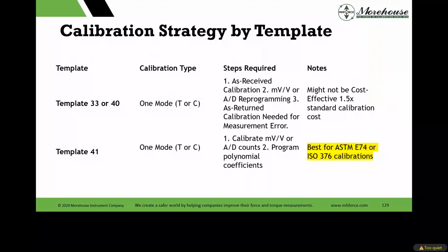So ideally, some of your problems with TEDS, which we started talking about bias and everything, is these templates, 33 or 40, the way TEDS is designed, is one mode. If I have a tension and compression load cell, unless I have a modified version of TEDS, I'm only able to program one mode. And the downside with a template 33 or 40 is when you send that off to be calibrated, chances of reprogramming are high, depending on what you want to do and how close you need to make it. And that might not be cost effective for you.